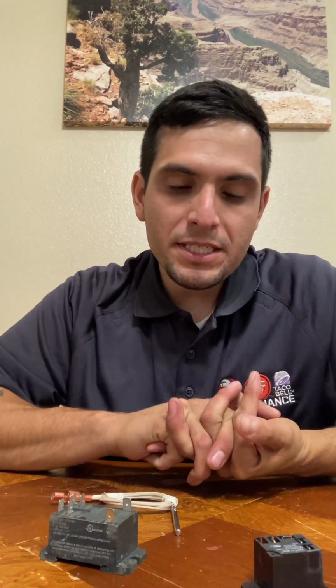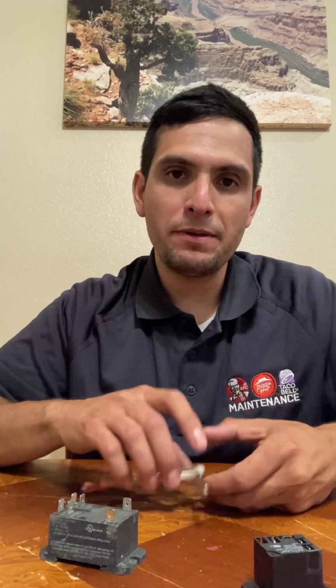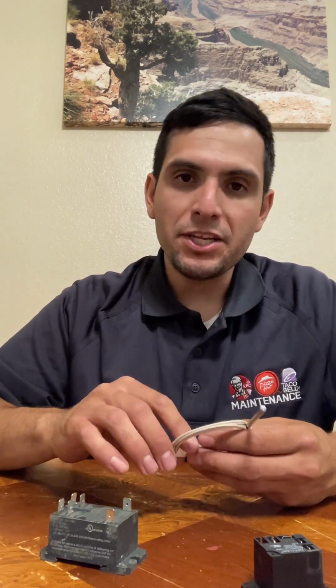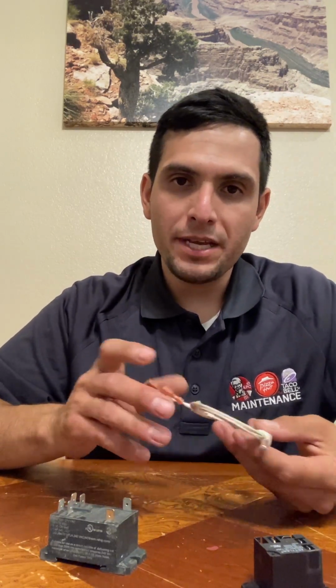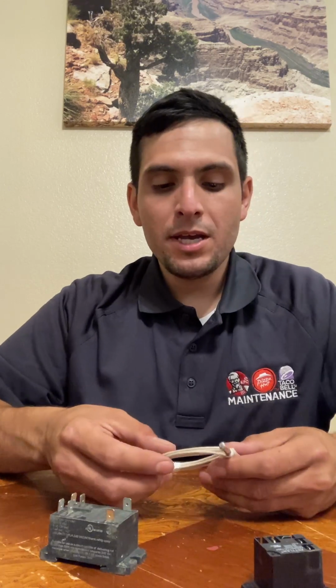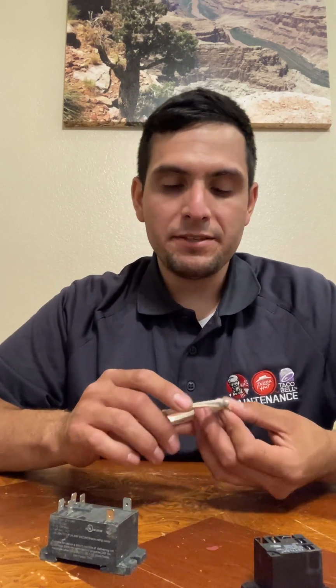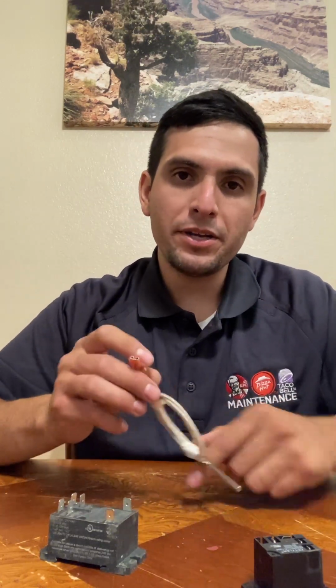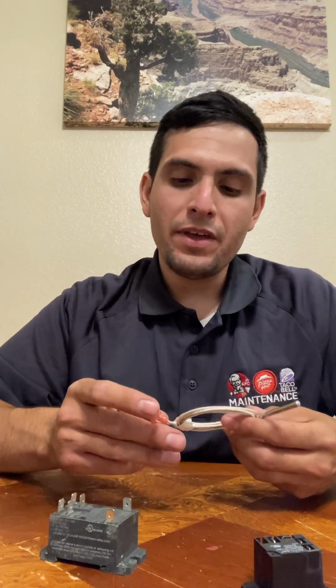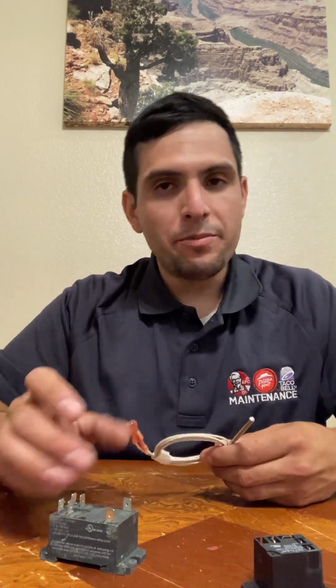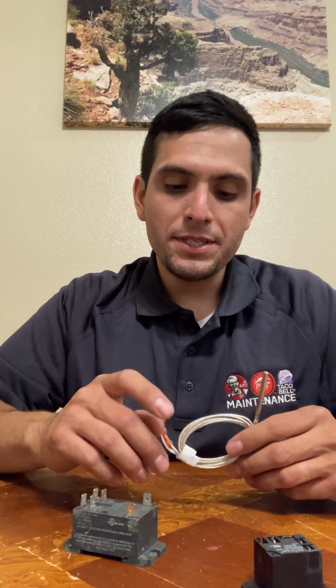The other thing to keep in mind is that even though it says probe 1, probe 2, probe 3, that doesn't mean it's necessarily the probe. I've seen a lot of techs immediately go buy a new probe, change it out, and it's the same problem. What can happen is if there's any wiring leading up to that probe, that can throw a probe fault. If there's a bad relay, that can throw a probe fault too.